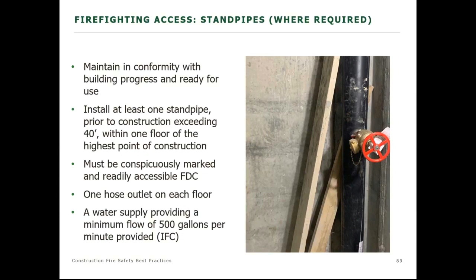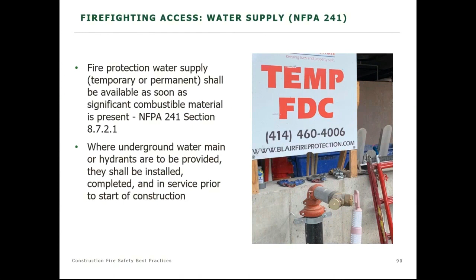But in Charlotte, they didn't have any standpipe. I saw the video and I heard the tapes of firefighters with high-rise packs going in, being ordered to hook up to the standpipe, and them saying there is no standpipe, so they had to back out and then stretch lines. Now, NFPA 241 just says you have to have an adequate water supply whenever combustibles get on site, but they don't give you any guidance on what that supply is, or what was adequate.